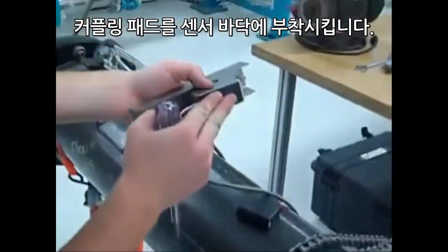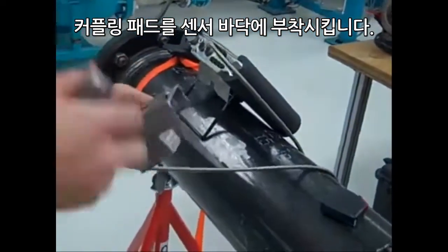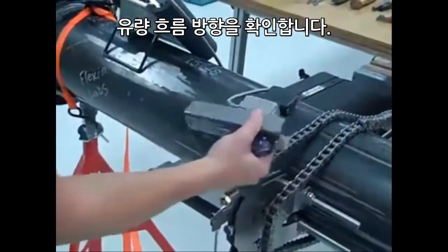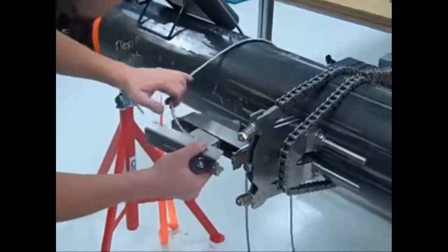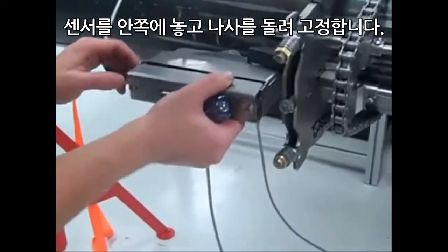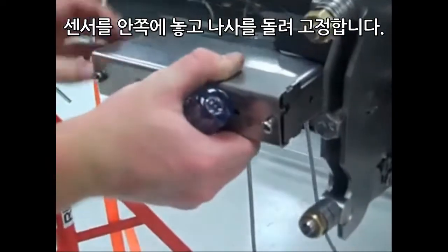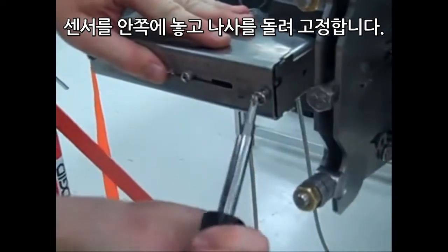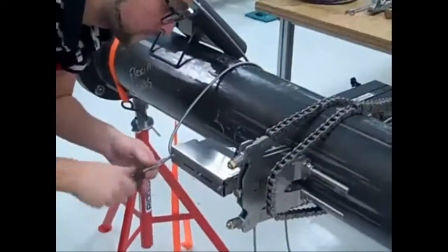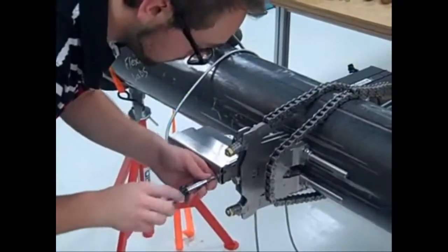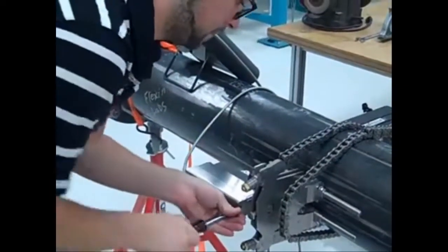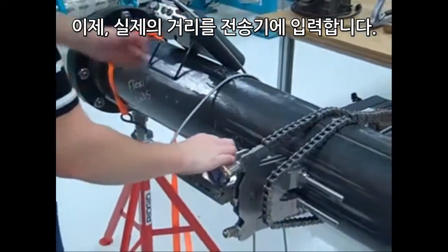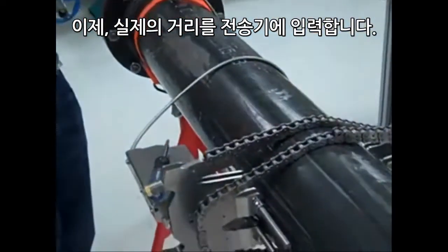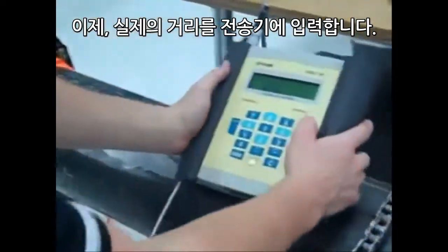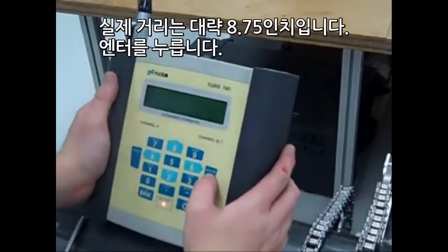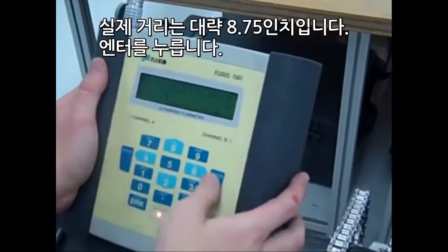Place the pad on the bottom of the transducers, pointing in the direction of flow, which is going to be right to left. Place the transducer inside and tighten down the screws. Next step is to insert the actual spacing of your transducers into your flow computer. Our spacing is about 8.75 inches.